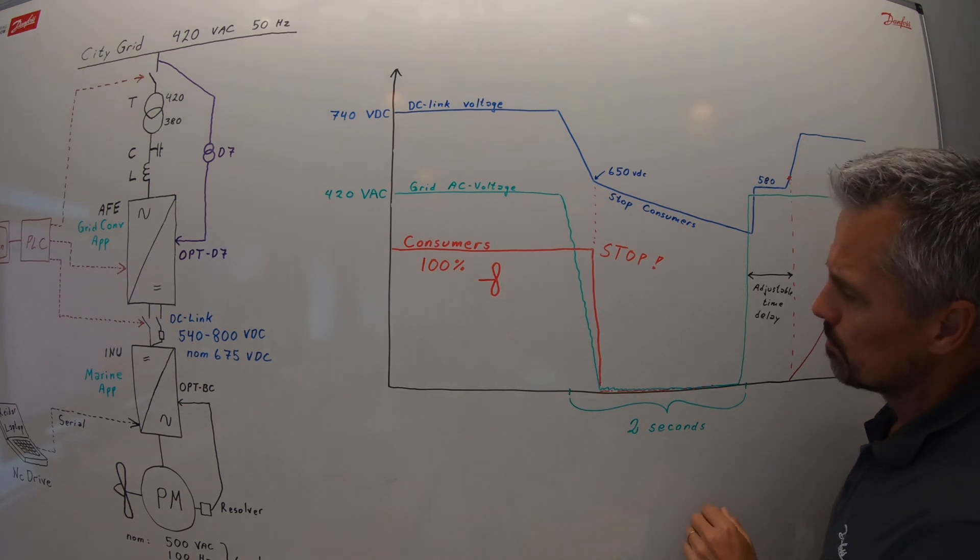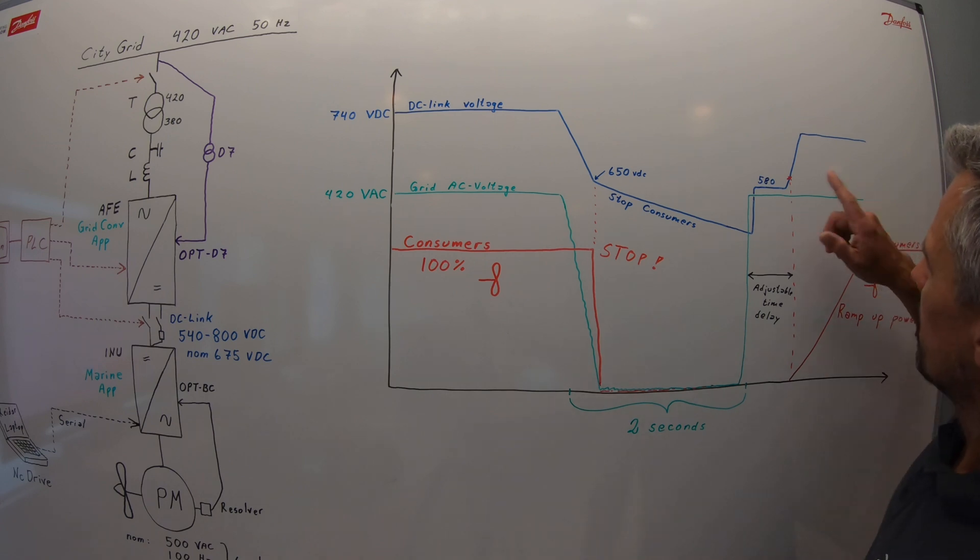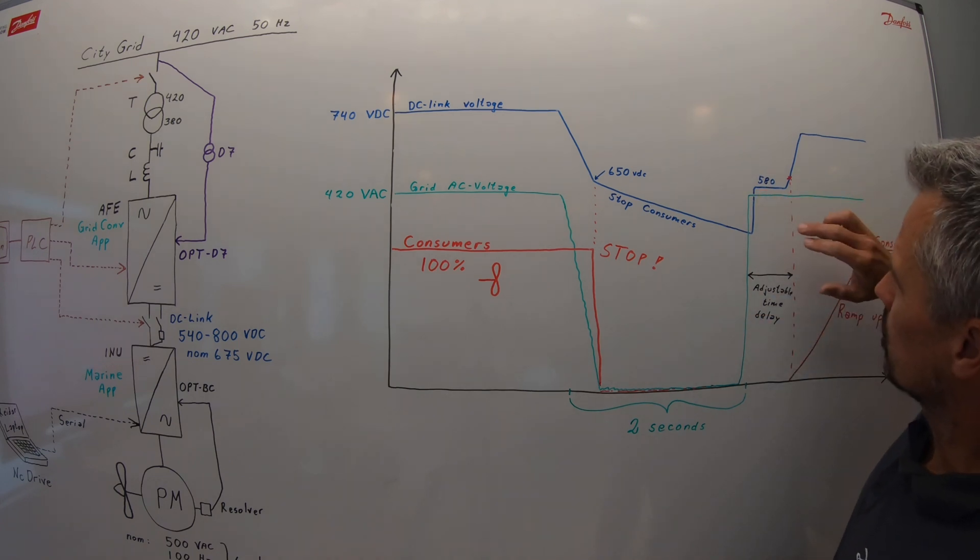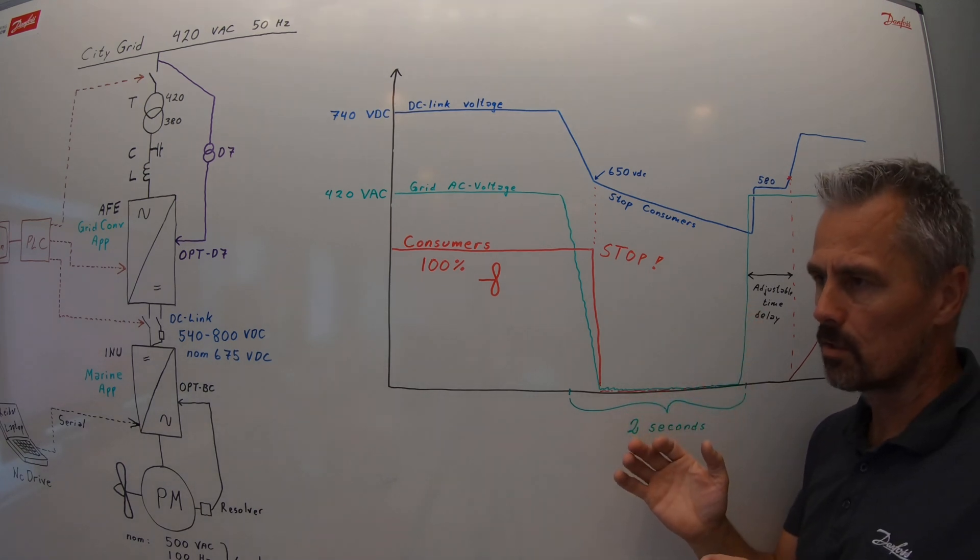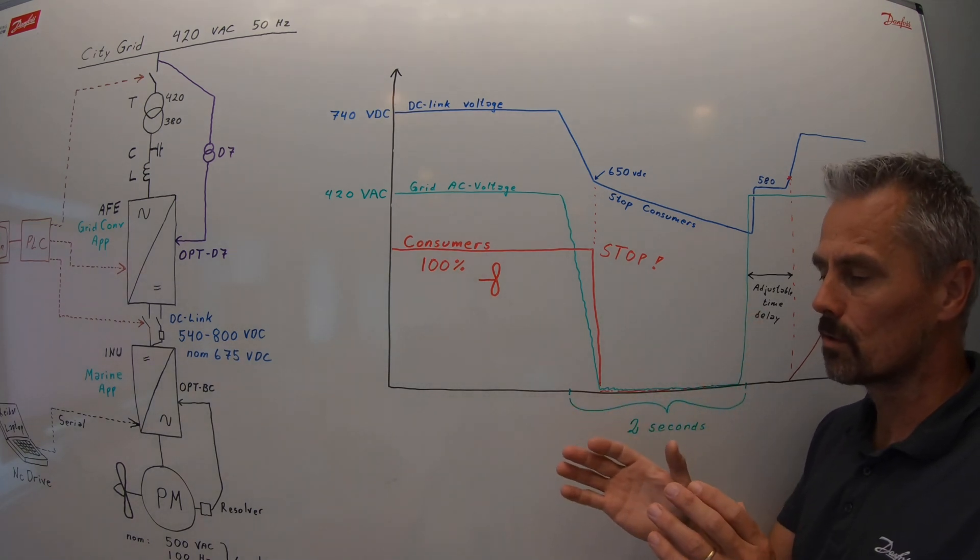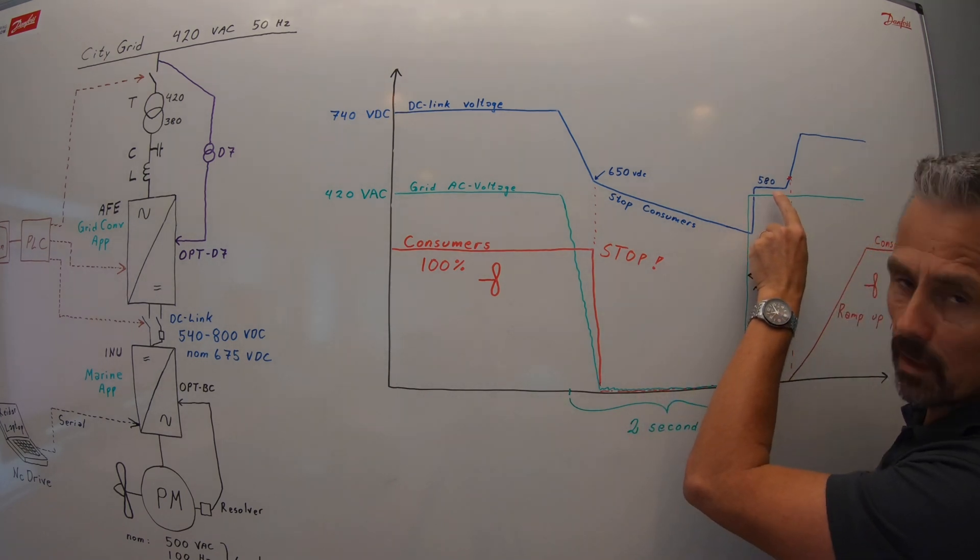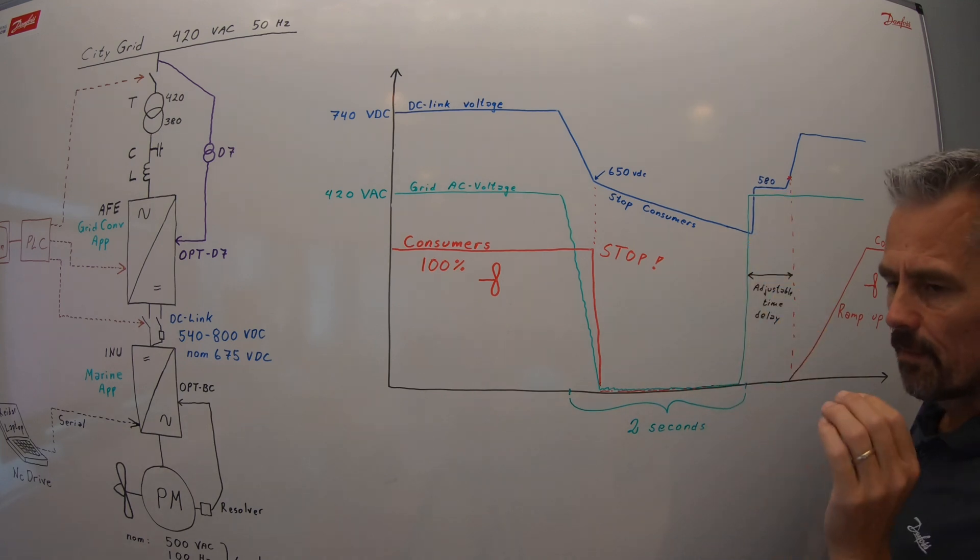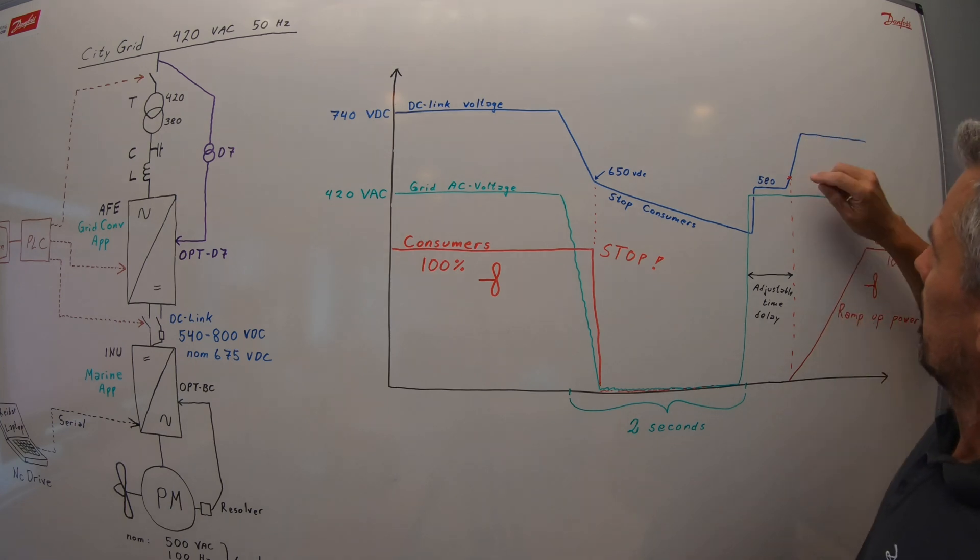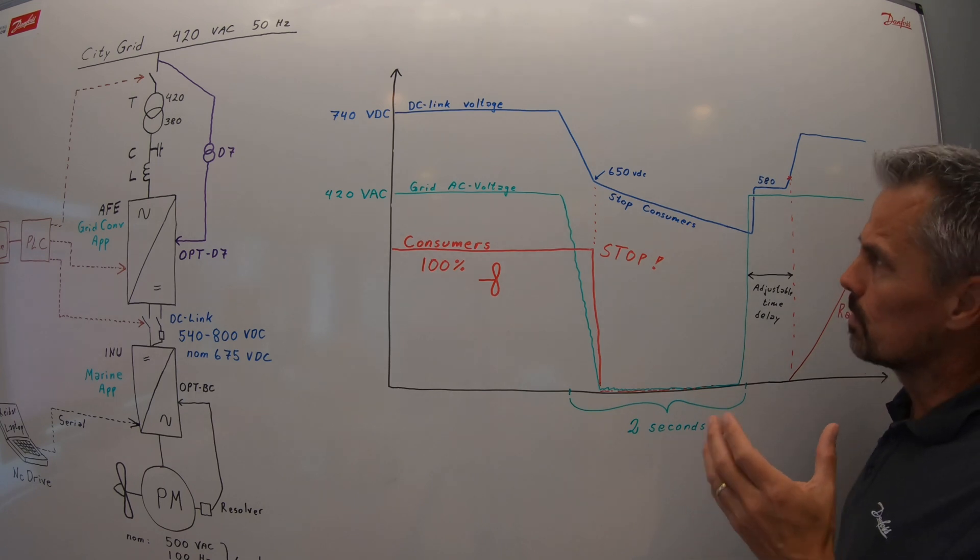After two seconds, that's the requirement from Veritas. Then the voltage on the AC grid comes back. The DC voltage will first start increasing from the pre-charge or from the freewheeling diodes through the grid converter. It will go up to the diode rectifier level, in this case 580 volts.